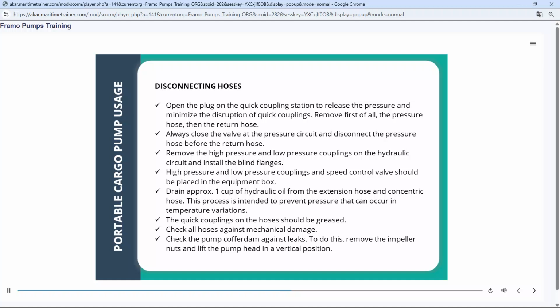Drain approximately 1 cup of hydraulic oil from the extension hose and concentric hose. This process is intended to prevent pressure that can occur in temperature variations. The quick couplings on the hoses should be greased. Check all hoses against mechanical damage. Check the pump cofferdam against leaks. To do this, remove the impeller nuts and lift the pump head in a vertical position.